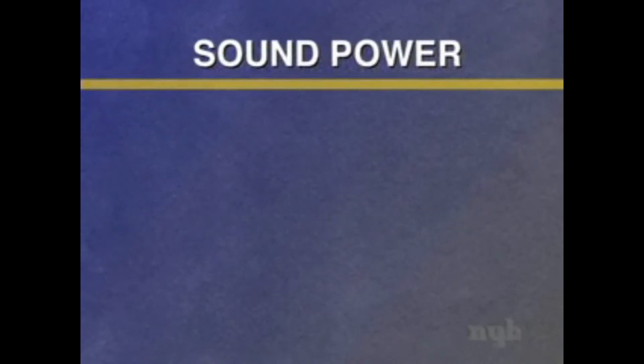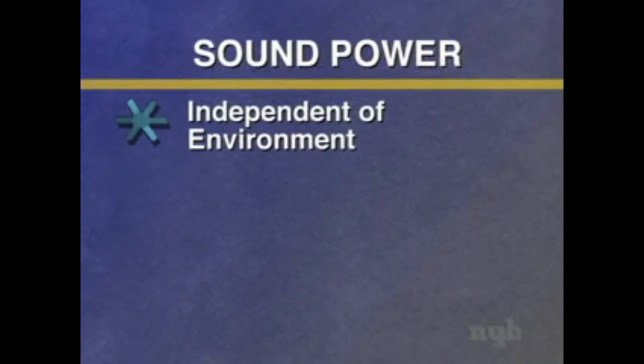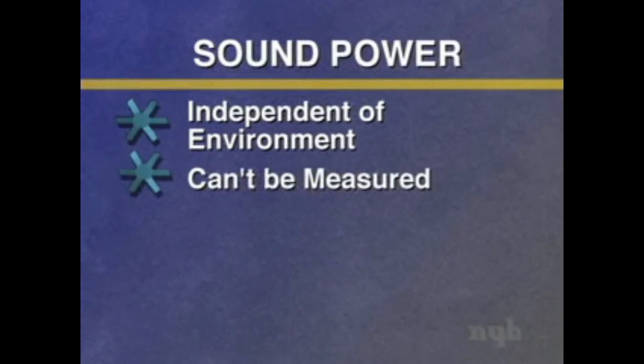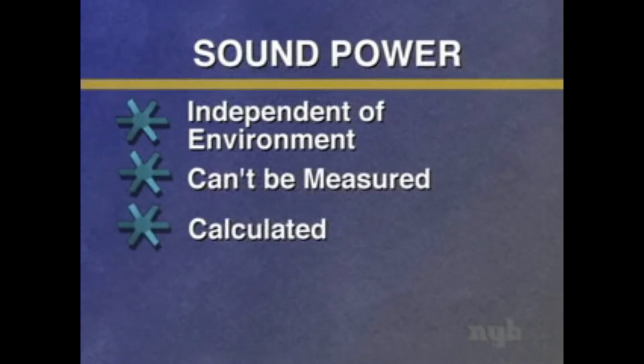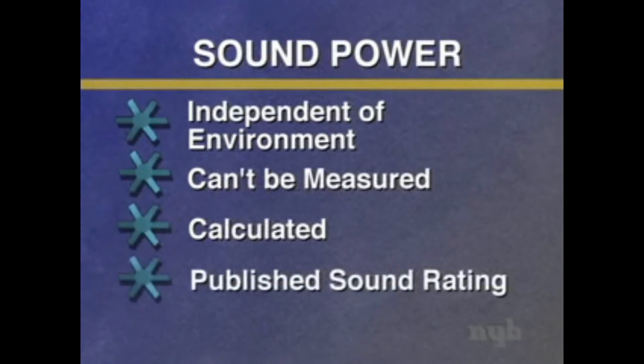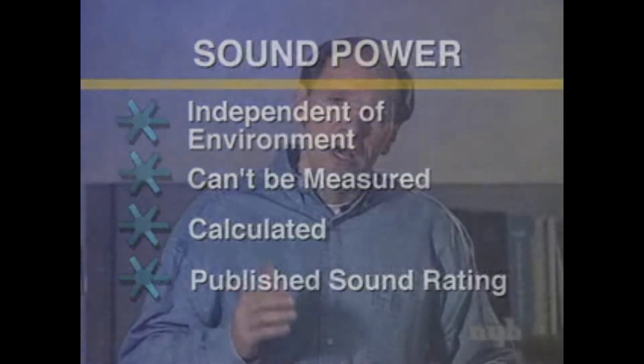Sound power, on the other hand, is independent of the environment. It cannot be measured directly. Sound power is calculated from sound pressure levels measured in a known environment. It is specific to a particular piece of equipment, and it allows manufacturers to publish ratings in a uniform way. Unfortunately, both sound pressure and sound power are referenced to the same type of generic mathematical scale, which adds to the confusion.